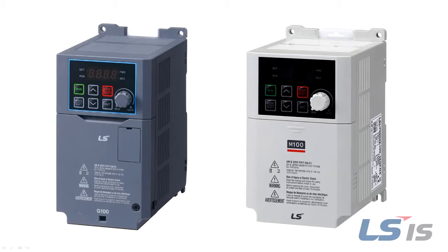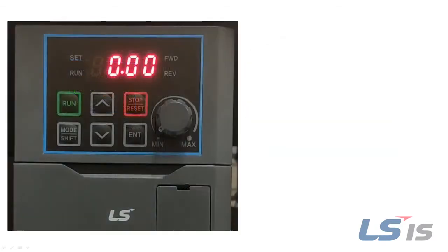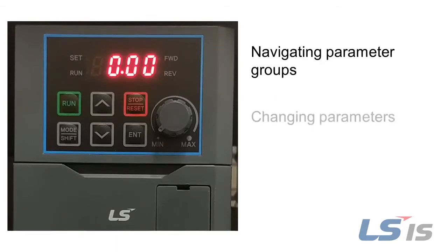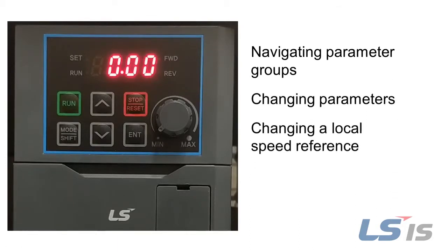In this video, we will demonstrate how to navigate the G100 and M100 keypads. This includes navigating the parameter groups, changing parameters, changing a local speed reference, and checking basic monitors. These instructions will be helpful for anyone who works with the LS G100 or M100 drives.